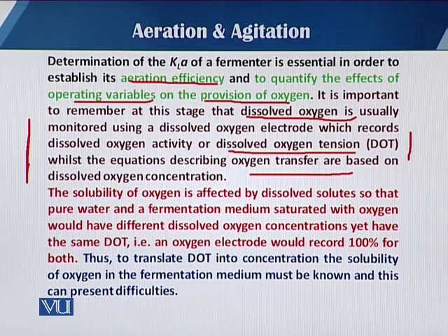The solubility of the oxygen is affected by the dissolved solutes, so pure water and the fermentation medium, saturated with oxygen, would have different dissolved oxygen concentrations, yet have the same DOT. The dissolved oxygen tension is the same, but the solubility has varied.